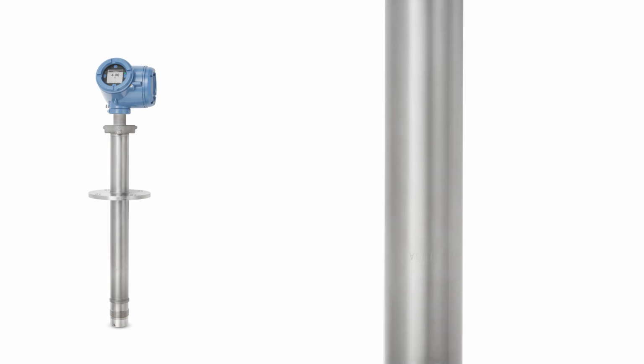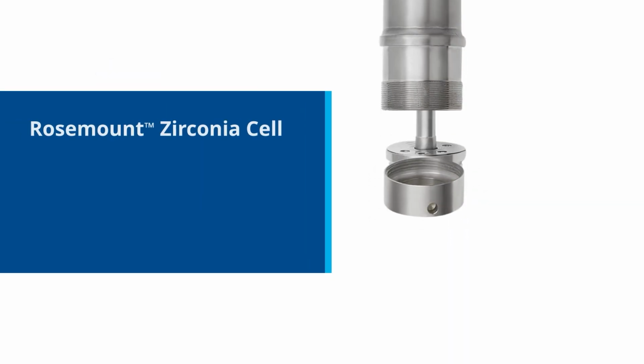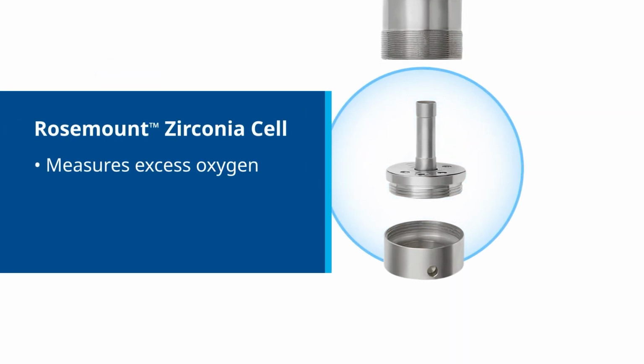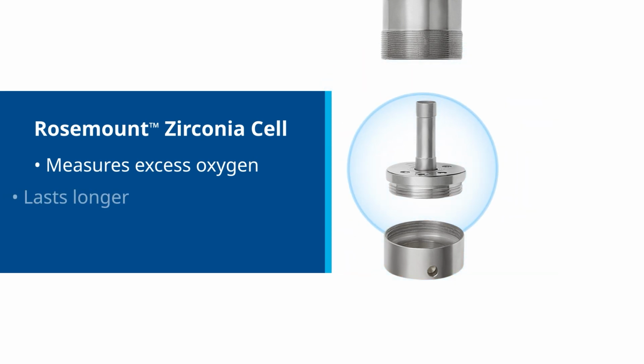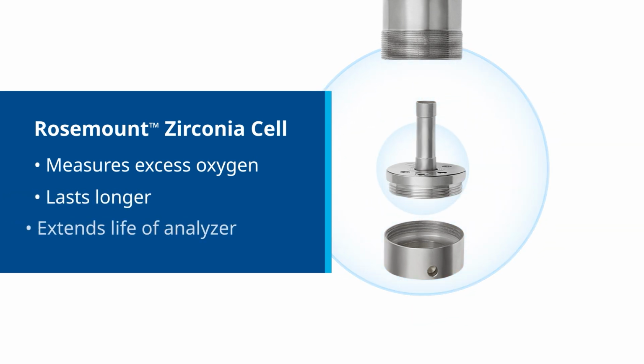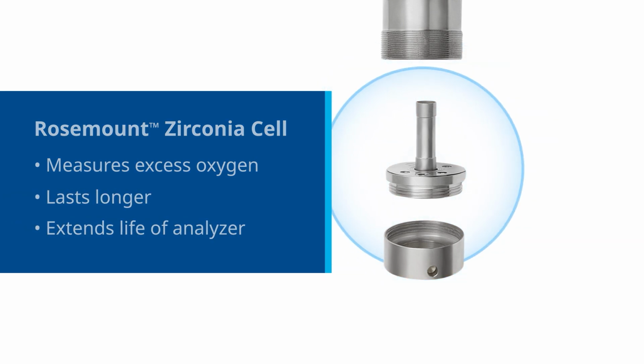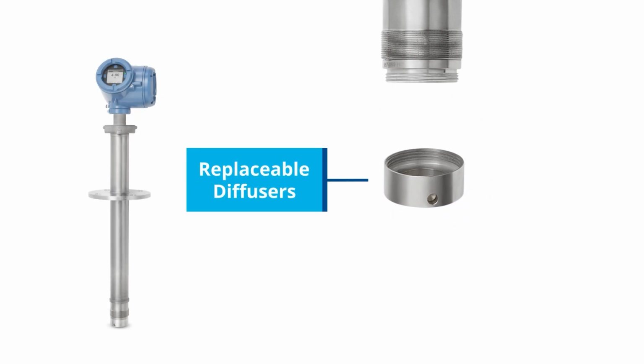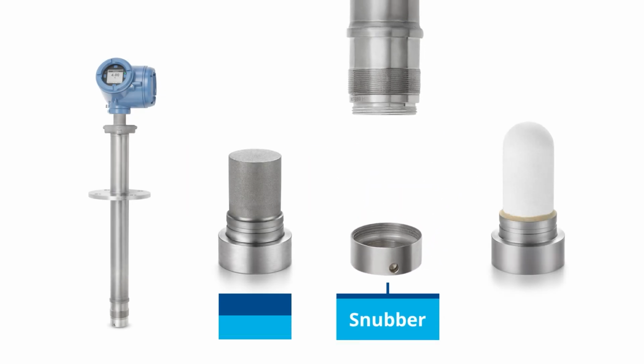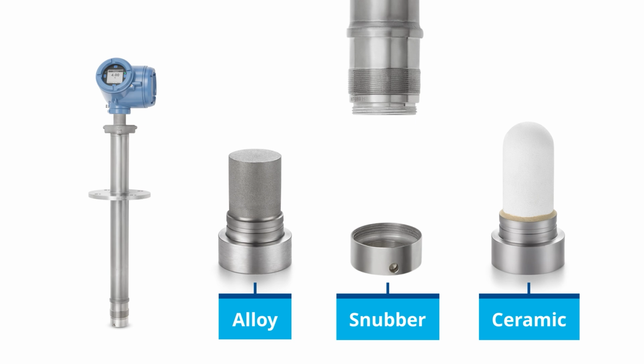Known for its accuracy, the Rosemount zirconia cell provides a continuous measurement of excess oxygen remaining in flue gases, is designed to last longer, and is replaceable to extend the life of the analyzer. Replaceable diffusers are available in stainless steel snubber, alloy, or ceramic styles to suit a wide range of temperature applications.